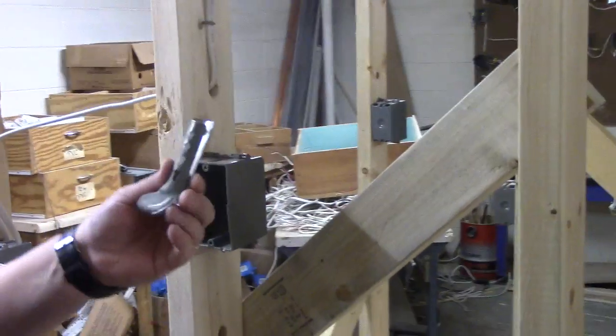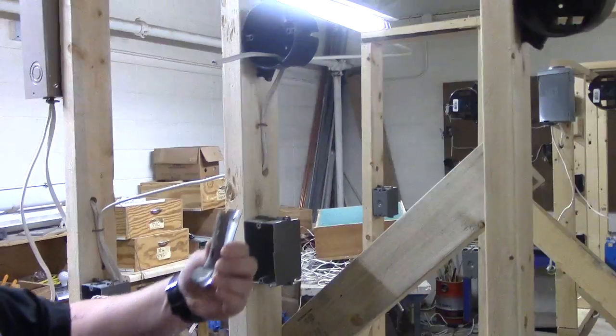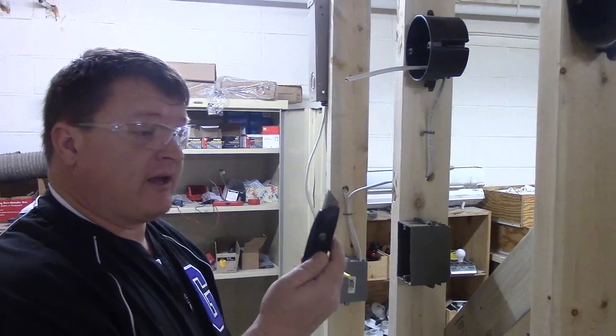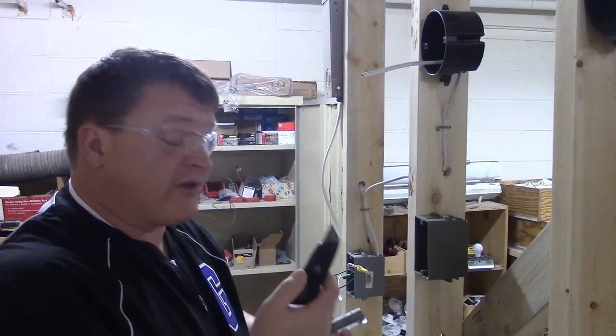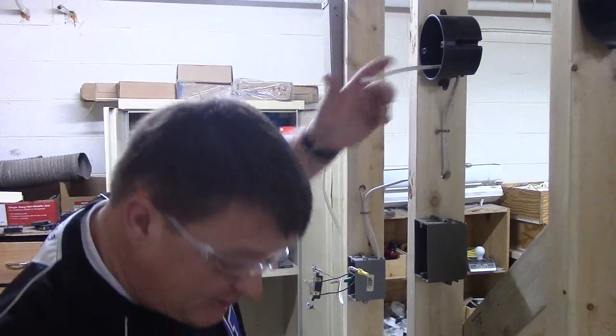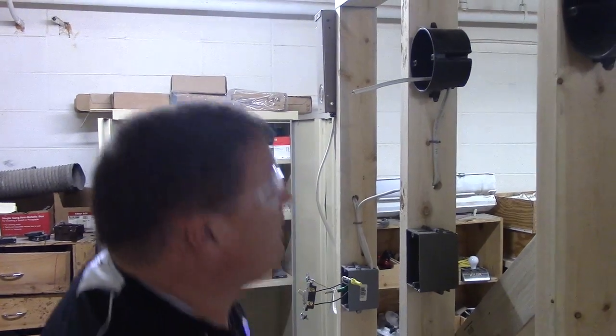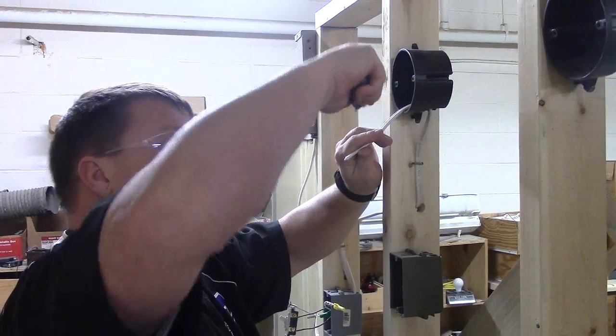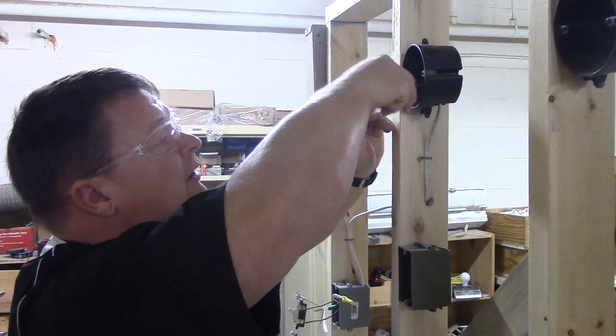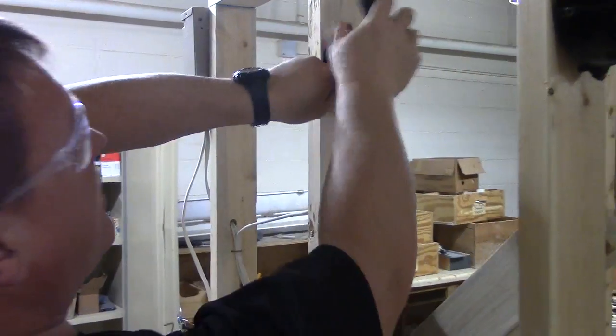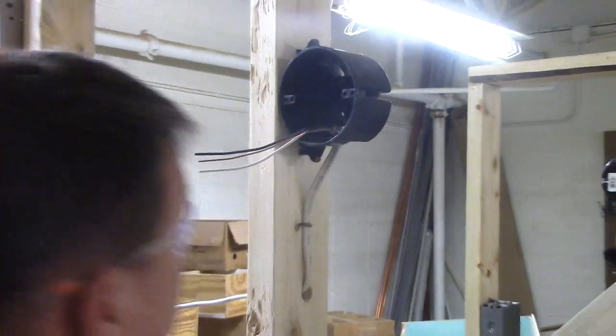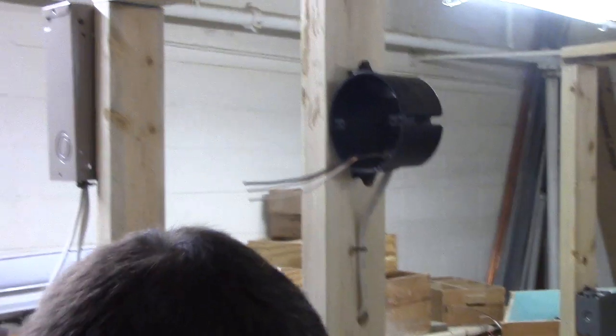Now if you don't have a ripper like I have here, you can pick these up at the hardware store or wherever, Lowe's, Home Depot, anywhere like that. They're a couple bucks, but you may just have a utility knife or a razor knife. These work also well for getting inside the box. But you have to be careful when you're cutting the Romex not to really dig in with it. Really all we want to do is score it. We're going to score the top, score the bottom, and the Romex comes right off. We're going to peel the paper off the ground wire and get it out of your way. It works out real well.